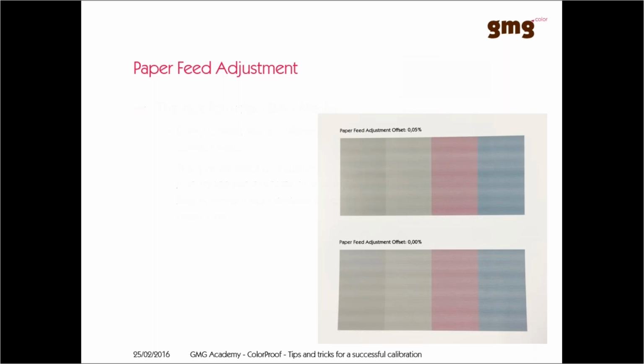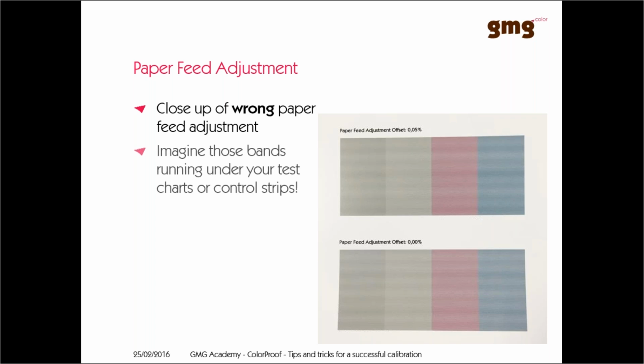Okay, so now we see an example of wrong paper feed adjustment. You see at the bottom of the test chart the paper feed adjustment set to 0%. This is the value which is set up in the software per default. So this is out of the box, and for some printers it may be completely fine having 0%. For some printers, as in our example here, it is not. Yeah, and imagine you have this banding on your test charts, on your media wedge, on your proofs, in your calibration. Not so nice.